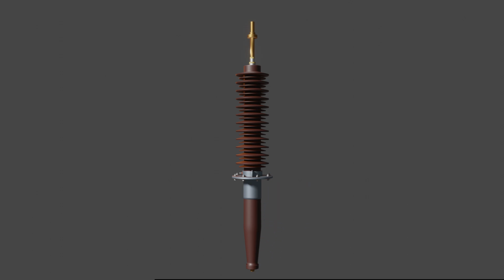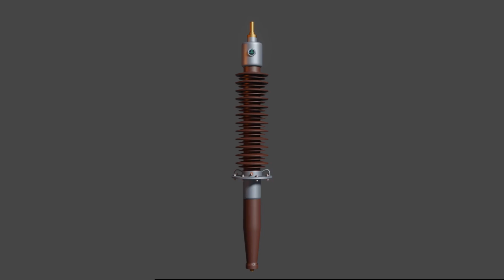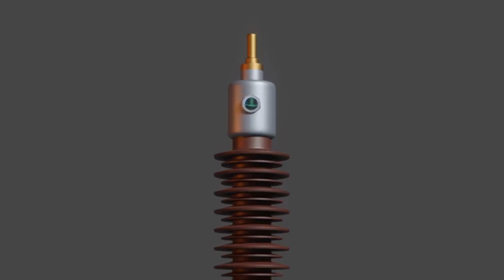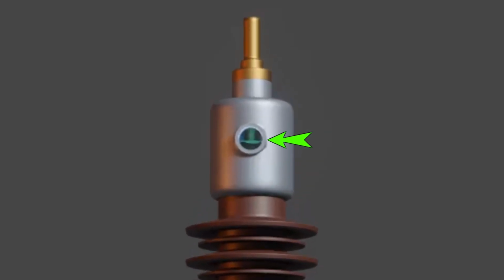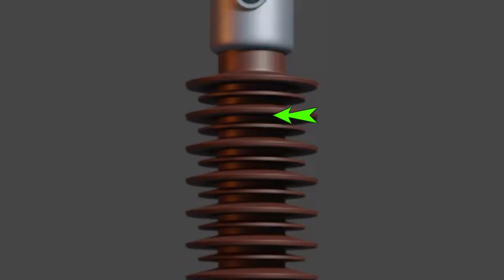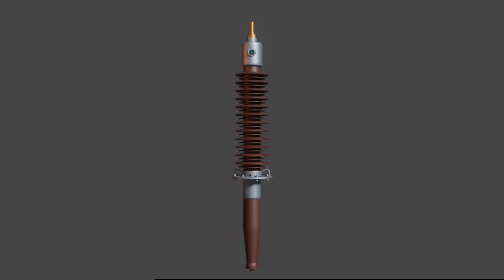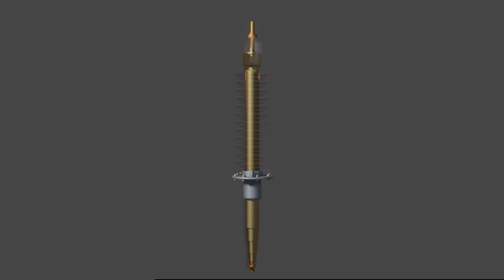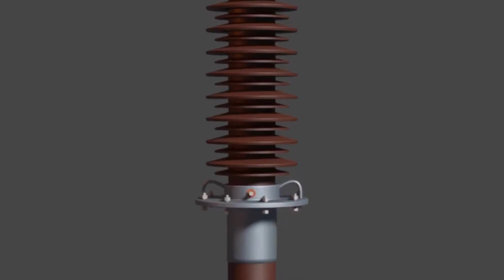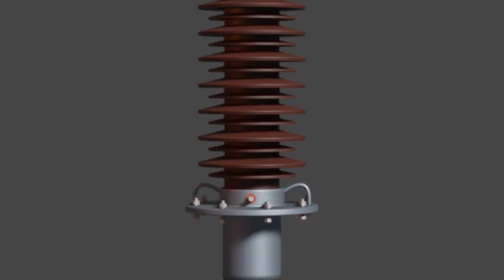Now we provide the expansion chamber on the top of the housing. This expansion chamber provides adequate space for the oil to expand and contract. This is the oil gauge from where we can visualize the level of oil inside the bushing. Actually, the bushing is hermetically sealed from that portion to that portion, and the entire housing is filled with oil up to this level. If we see only the oil inside the bushing, we observe that the entire condenser arrangement is inside the oil, and the oil is up to this level. These two are the hangers fitted on the flange to handle the bushing.